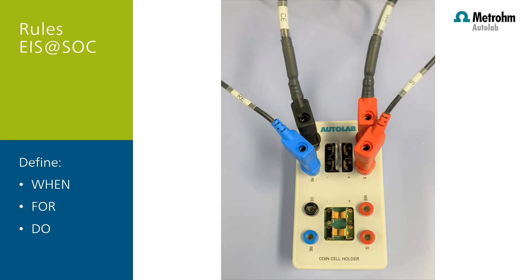For example, the potential of a battery during a charge or discharge cycle. In a rule option, the user has to define the 'when' — it defines the signal on which the rule is applied, and it defines the difference in circumstances needed to trigger the rule, for example the greater than or less than signs. The 'for' defines the number of consecutive samples required to trigger the rule.